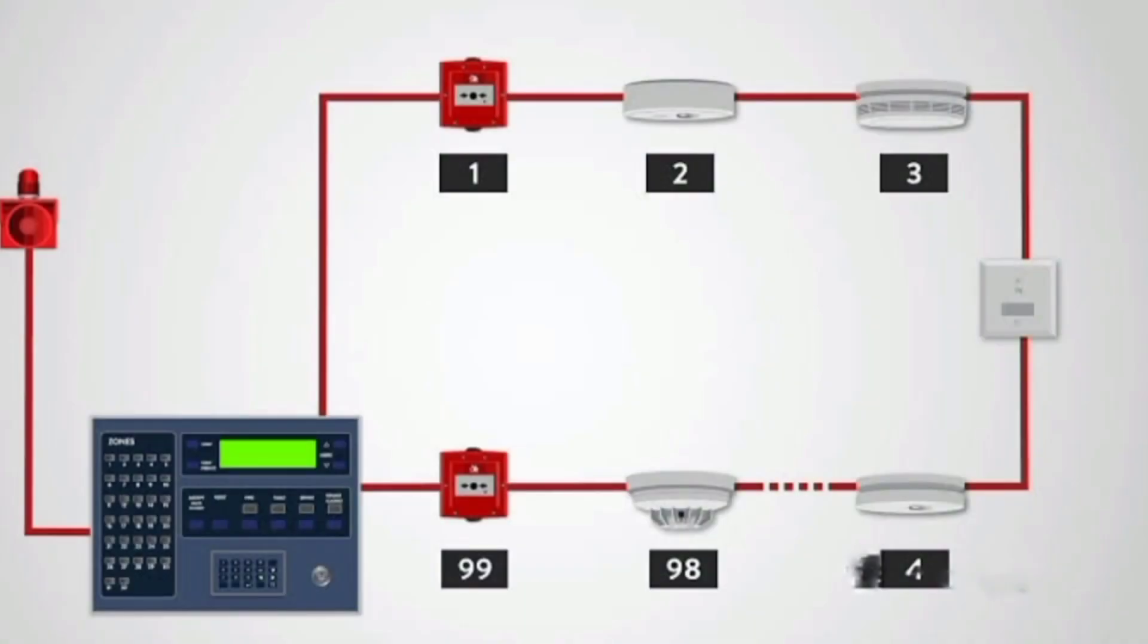The detection principle of an addressable system is the same as a conventional system except that each detector is given a set address, usually by means of a DIP switch, and the control panel can then determine exactly which detector or call point has initiated the alarm.